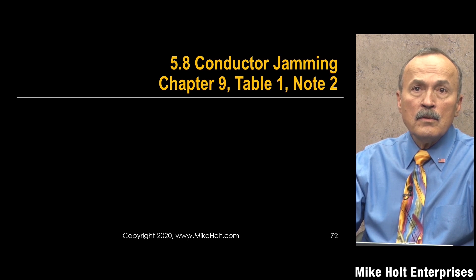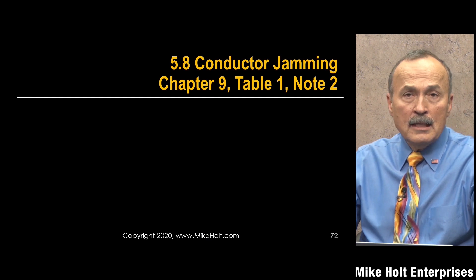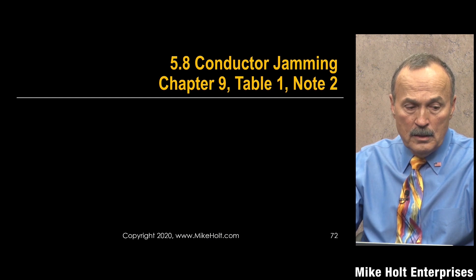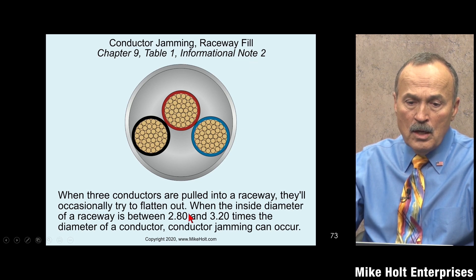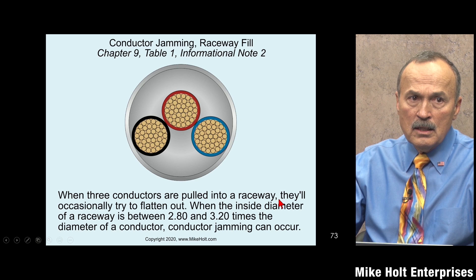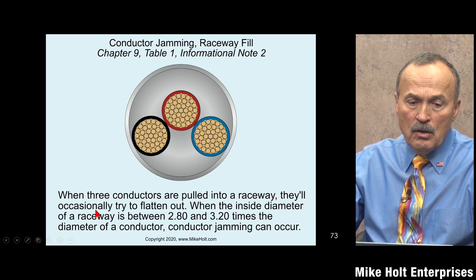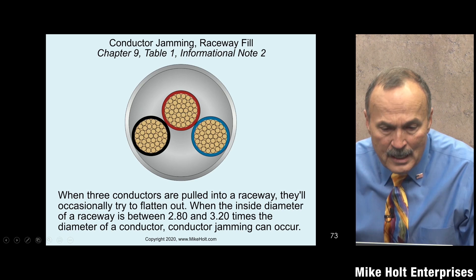Moving into conductor jamming — NEC Chapter 9, Table 1. There's an informational note to that table: Informational Note 2 states that where three conductors are pulled into a raceway, they will occasionally flatten out when the inside diameter of the raceway is between 2.8 and 3.2 times the diameter of a conductor, and conductor jamming can occur.